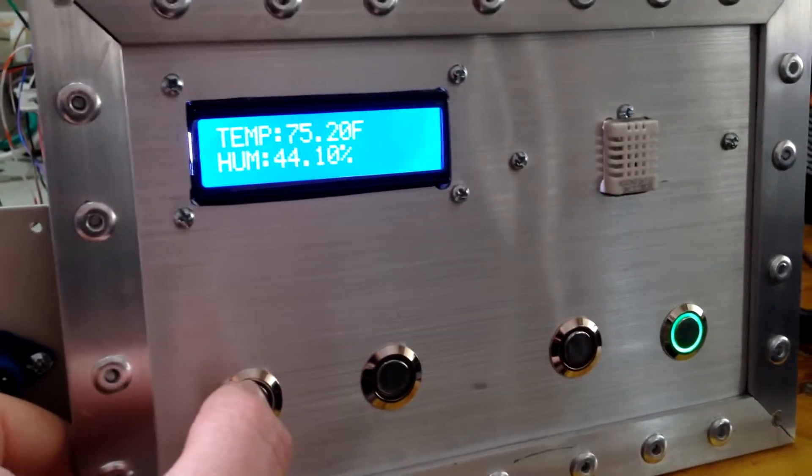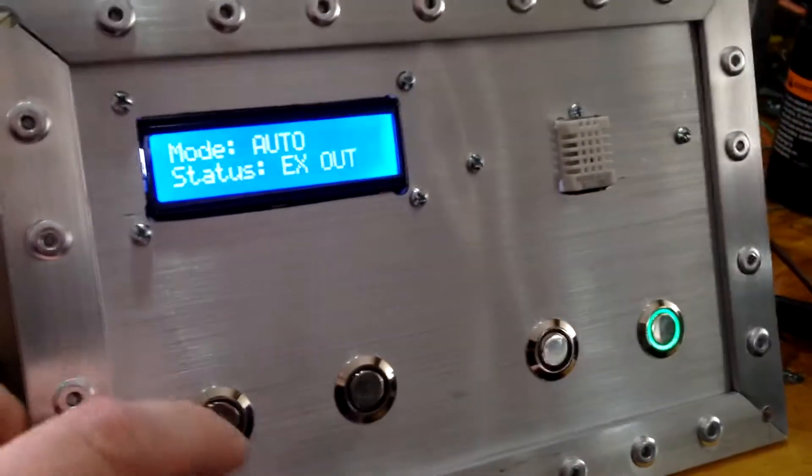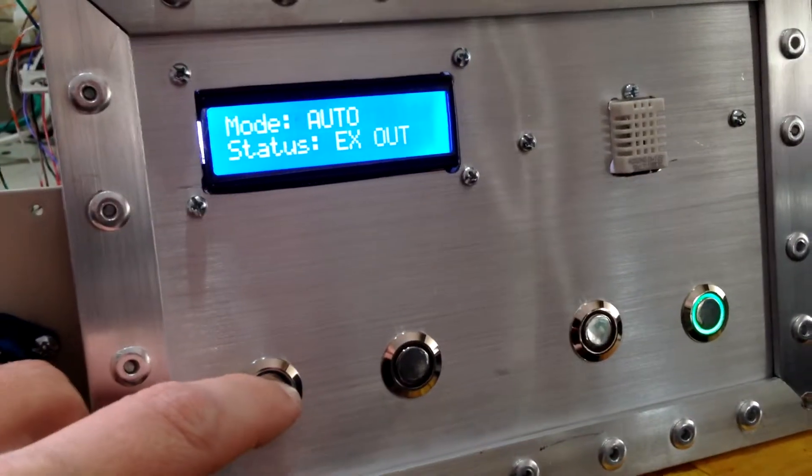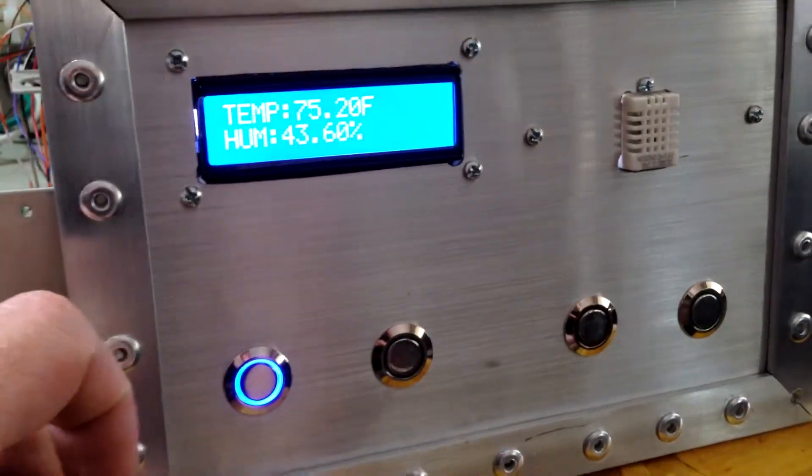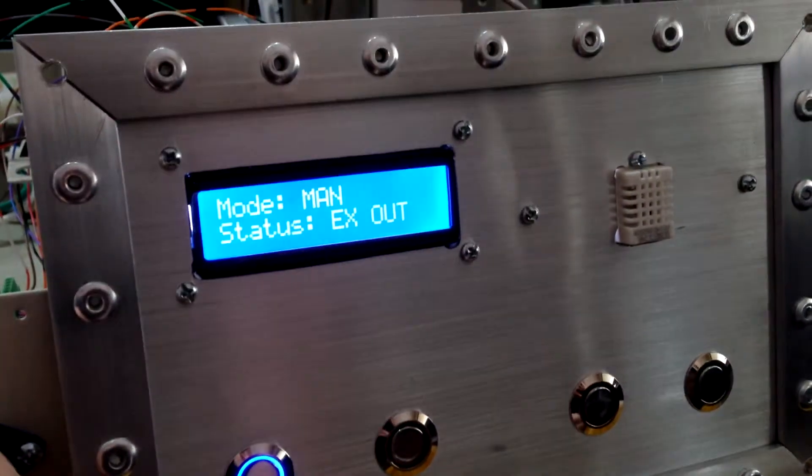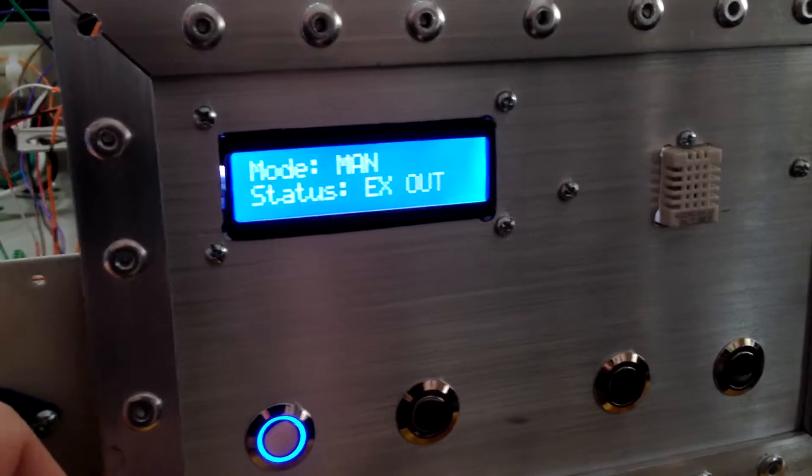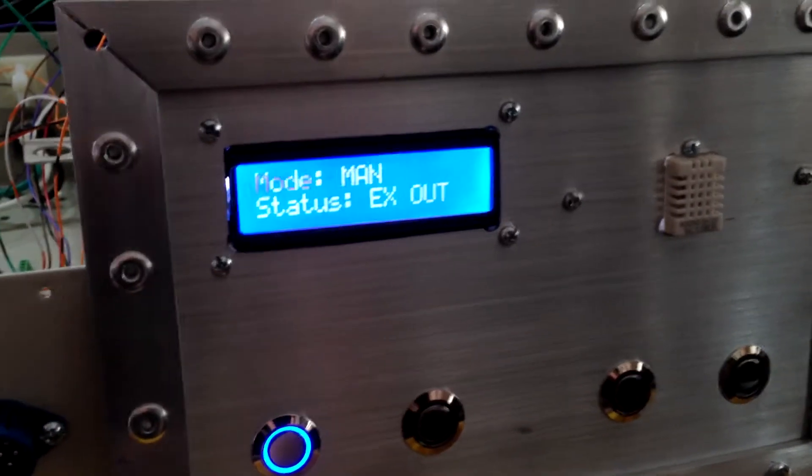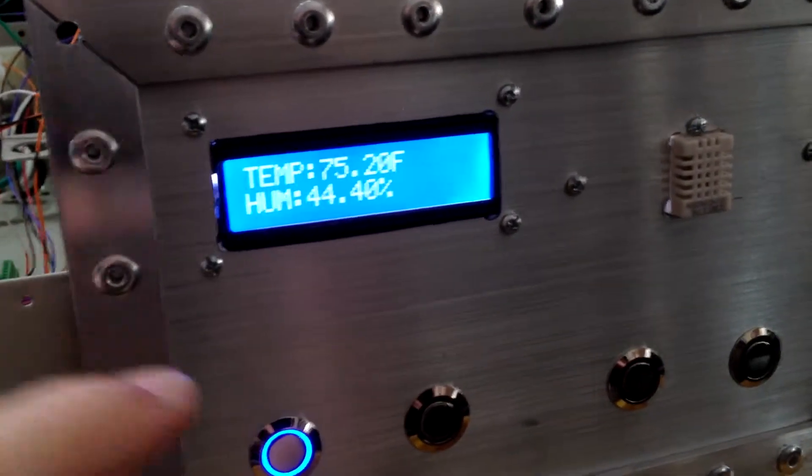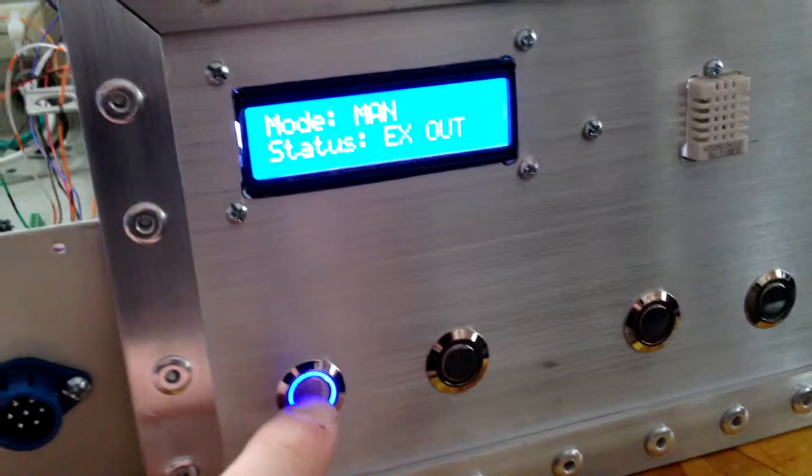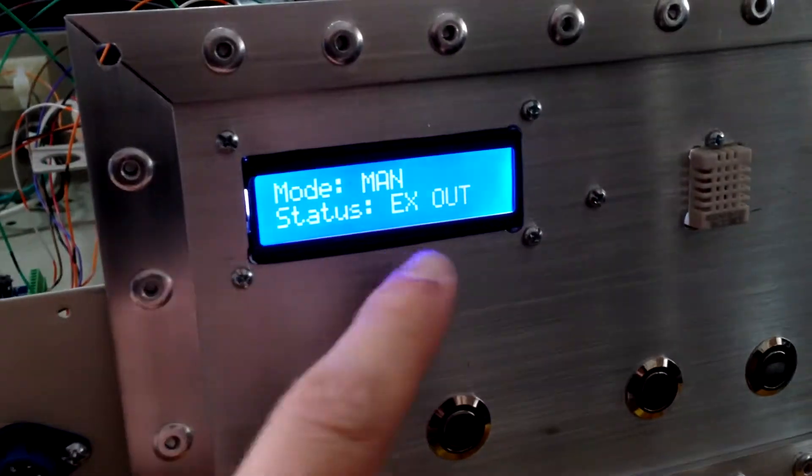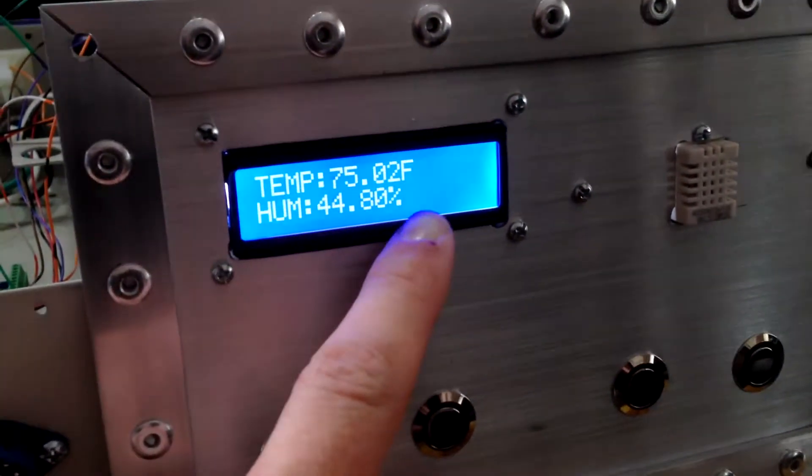It's already exhausting out. But if I hit the button here and tell it to go to manual, it's actually going to stay in this mode no matter what. If the temperature goes below 75, it doesn't matter. This is in manual mode. It's going to stay in this mode, exhausting outside no matter what.